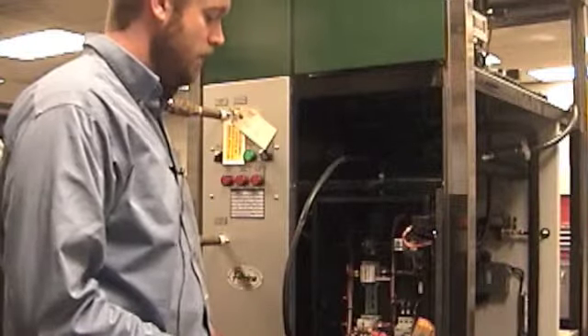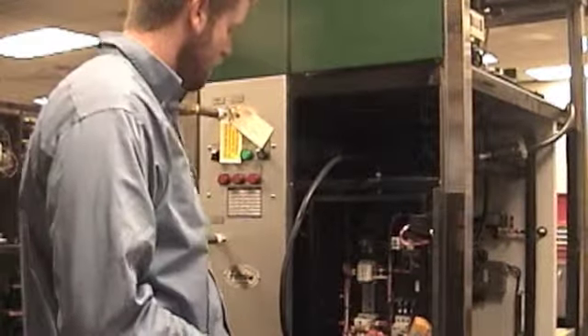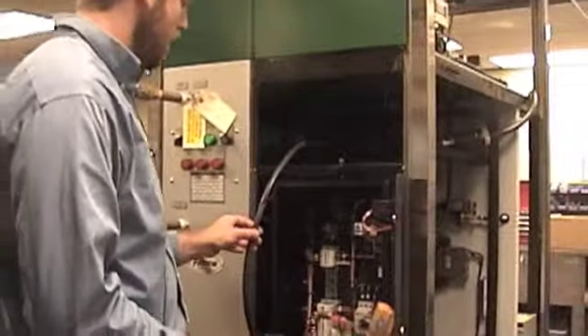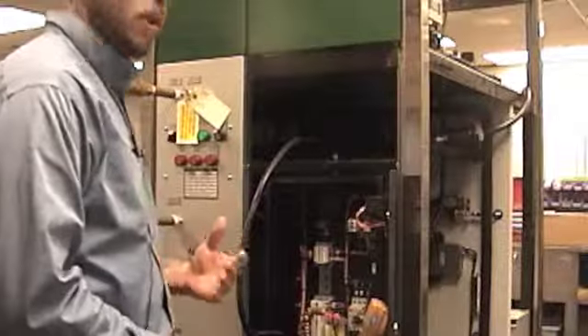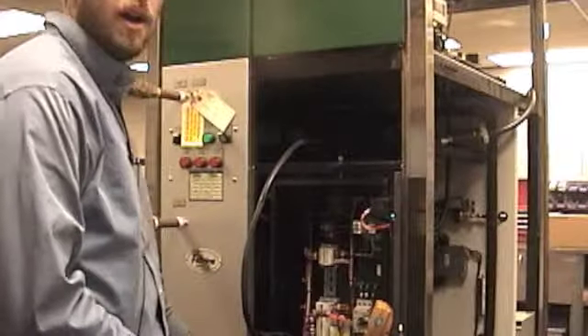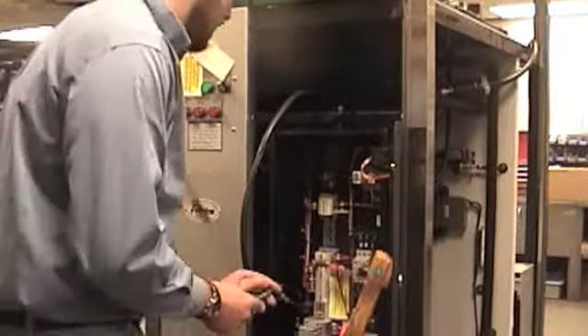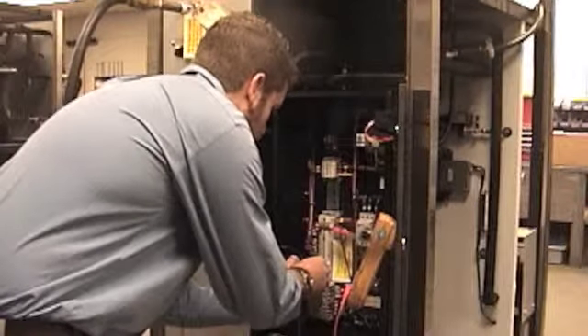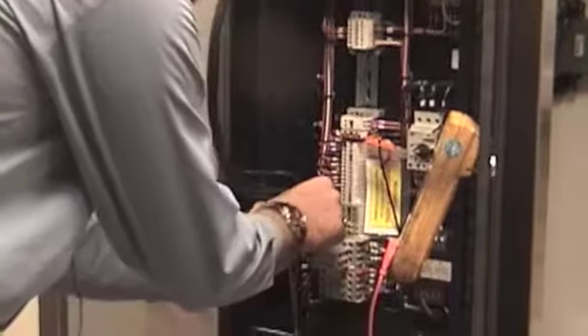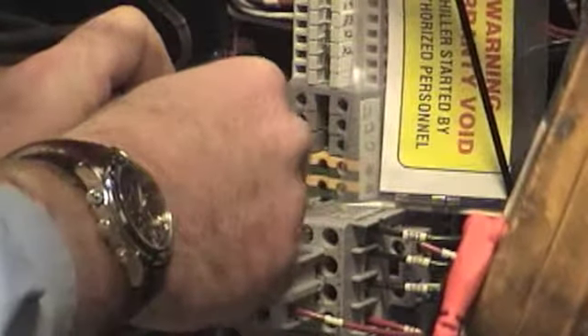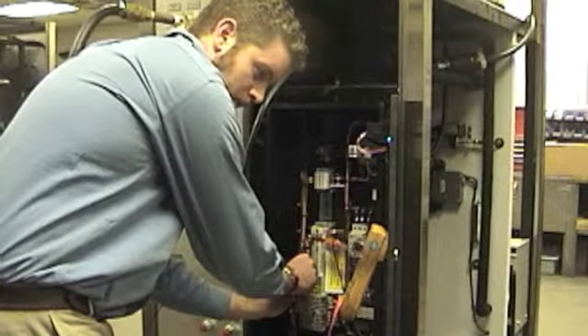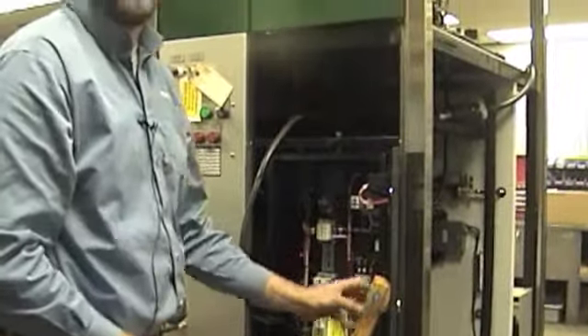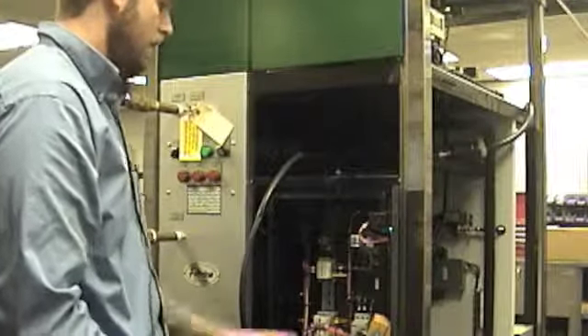So next we're going to check the voltage on the unit, make sure that that's correct. Once you turn it on, obviously we have our whip right here in the field. If this was in its final location, you'd have it hardwired through one of these knockouts. But to test the voltage, this is a 480 volt system, so you want to make sure you test each leg against each other, make sure they're all connected properly and showing 480 volts on your voltmeter, which they are, so we should be good. Make sure it matches the tag on the inside of the unit indicating that 480 voltage.